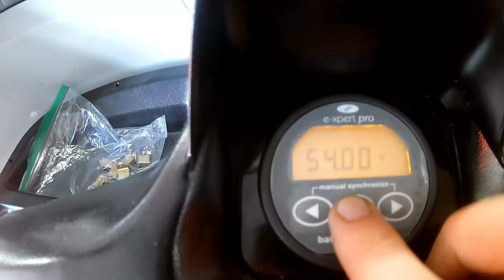Section 5.0 through 5.5 are programming the battery properties. This should probably be the first section in my humble opinion, but here it is near the end. The battery manufacturer rates my batteries as 100 amp hour capacity with a continuous discharge rate of 1C. So in section 5.0, we set the rated energy to 100 amp hours, which I already did because, again, this should come first.